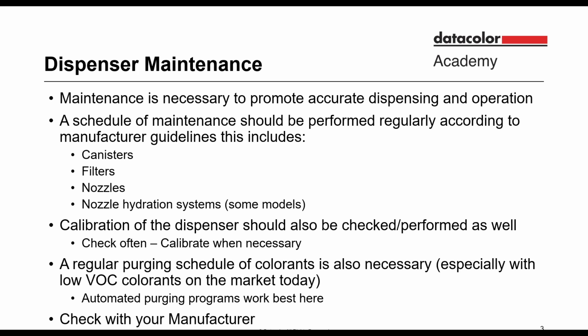An example of this would be to have a 1-ounce cup where you could put underneath each nozzle, dispense 1 ounce, and make sure that it's coming out within a plus or minus of that particular ounce. And that way you know that before the shift or the day begins, that your dispenser is dispensing accurately. You'll also know if you do this on a regular basis whether or not a particular canister is going to need to be either cleaned or calibrated in order to rectify the problems that you're seeing if it doesn't check calibration amount correctly.